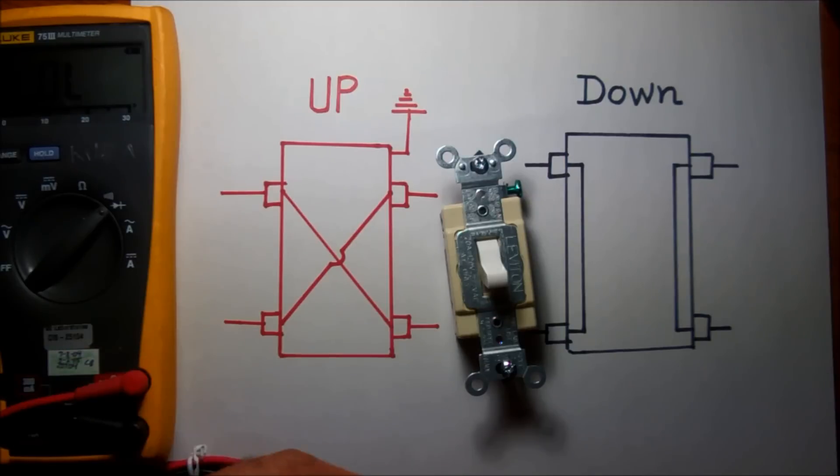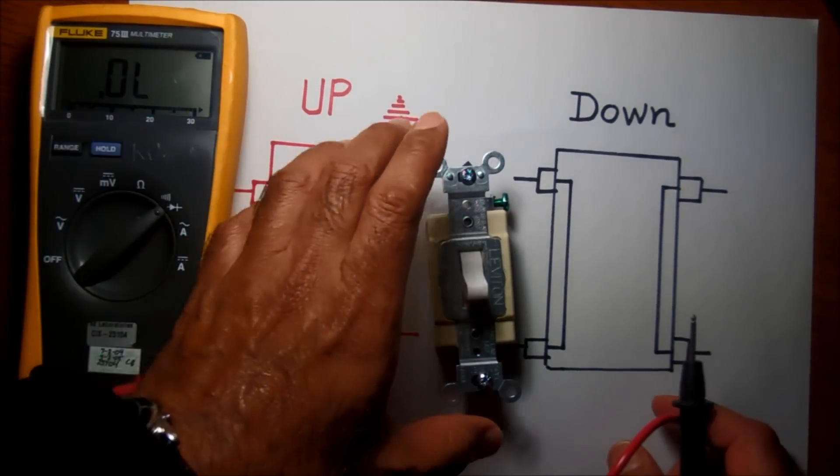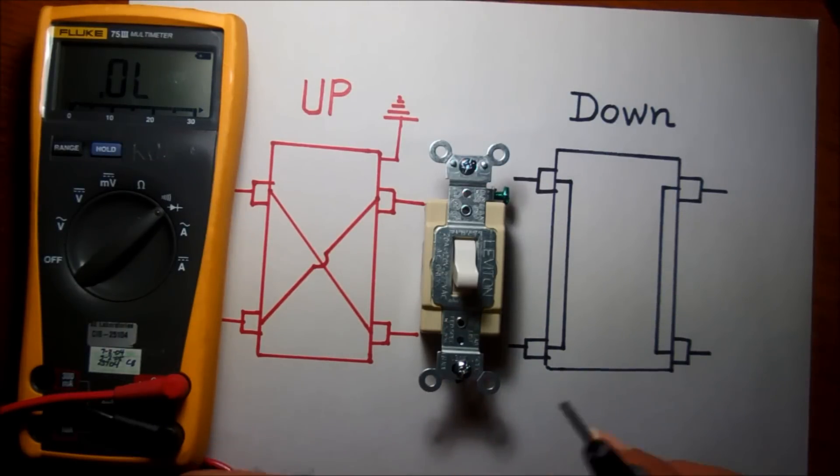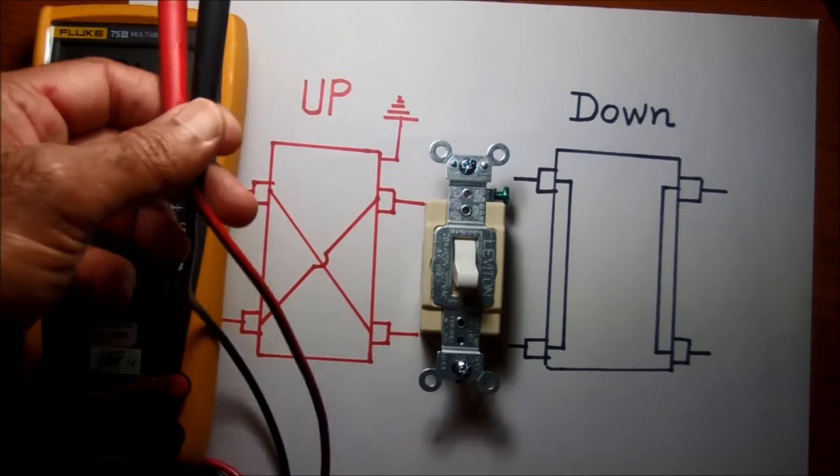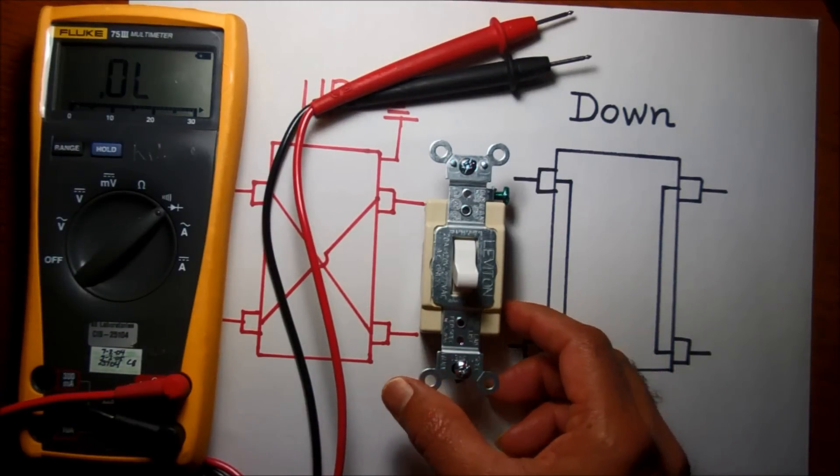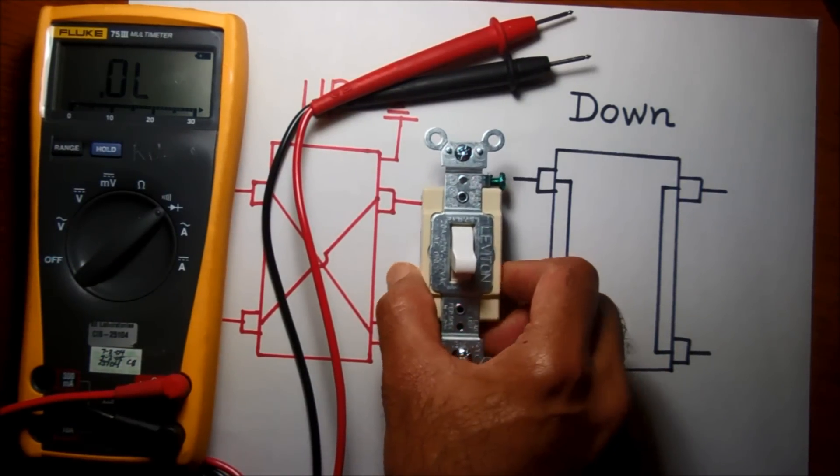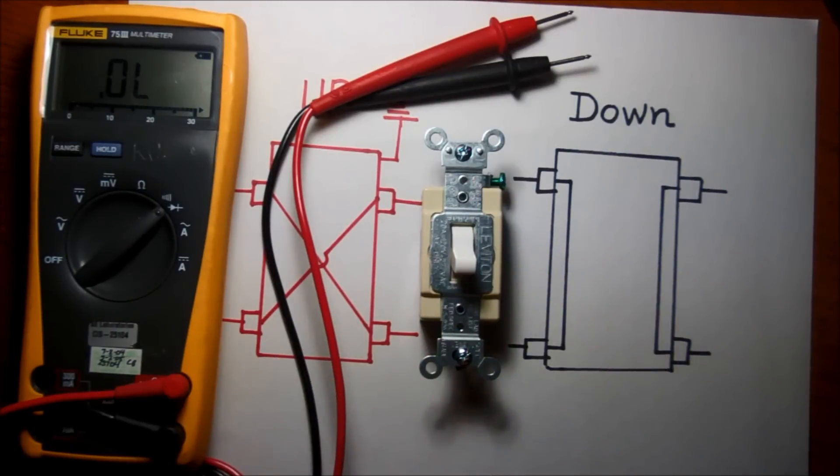The application of a four-way switch is when you want to control the light from more than two locations. If you want to control one light bulb with two switches, you will use three-way switches. If you want to control from three places, you need this four-way switch and two other three-way switches.